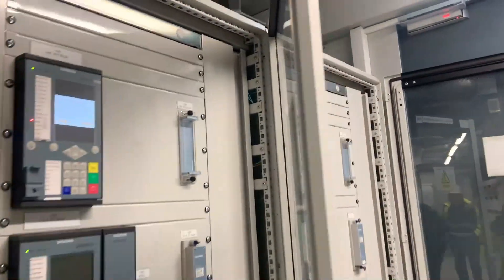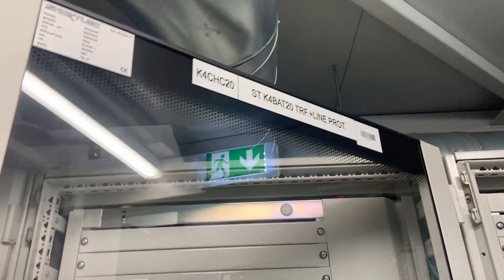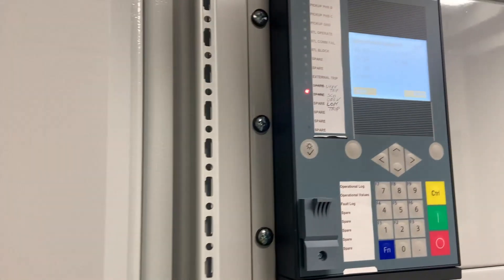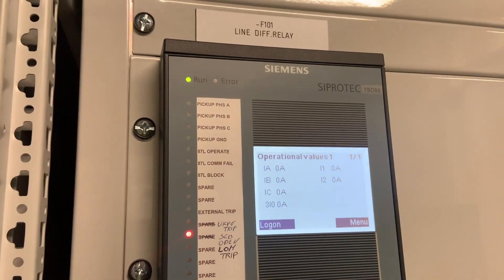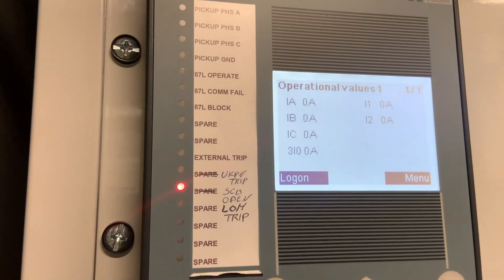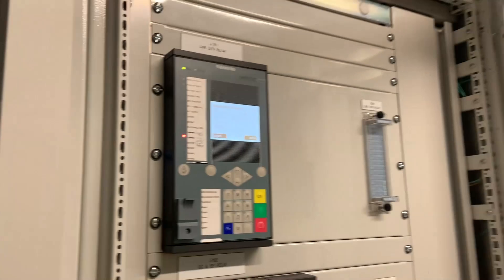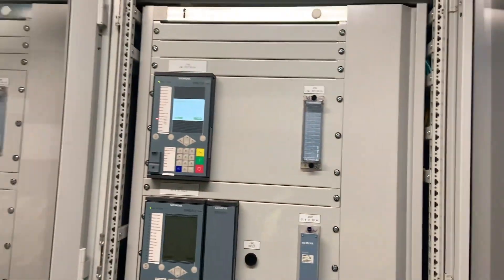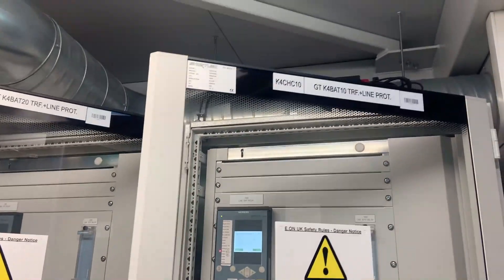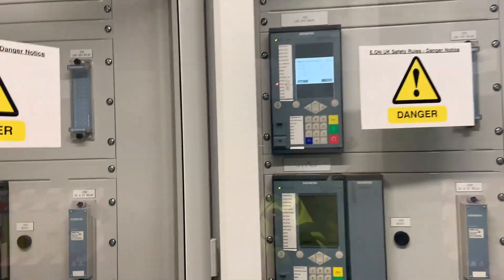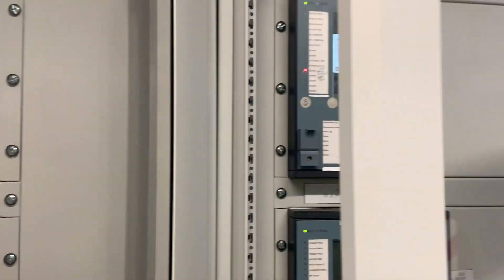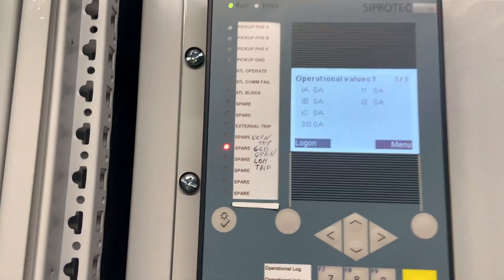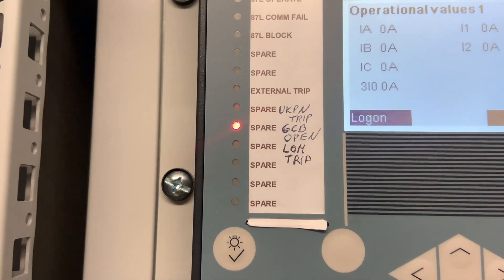The four trip signals now have to be communicated to the EON site to operate and open the 11kV generator circuit breakers. This is achieved with the line differential relays where the signals are repeated. The trip signals are sent across the fibre optic network to allow for the extensive distance between the two substations. We now have to repeat the four tests again, triggering them at the 33kV substation to make sure we successfully receive them at the EON site.